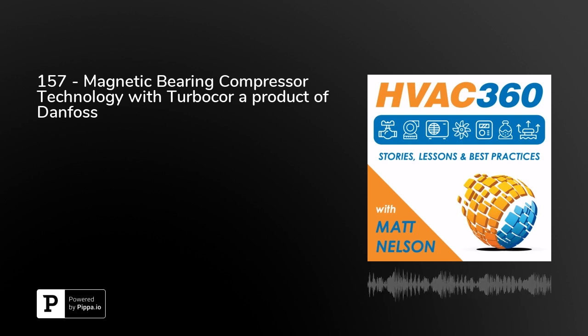What's the life expectancy difference between a screw and a Turbocor? With regards to our compressors, you can expect a 20-year lifespan with our technology. There's no reason why you can't achieve that with the recommended maintenance procedures. The difference is that a lot of the maintenance tasks you would commonly see on an oil compressor, such as changing the oil filter and monitoring oil in the system, are no longer required on our technology.